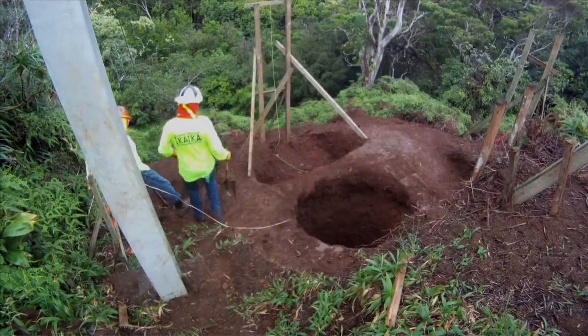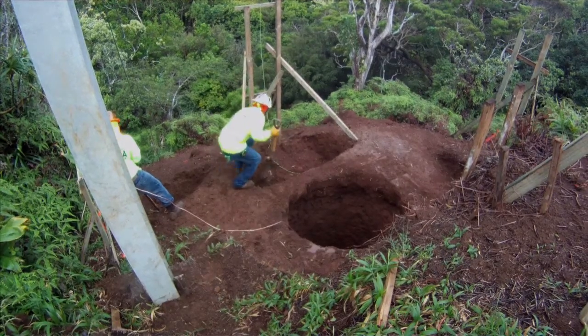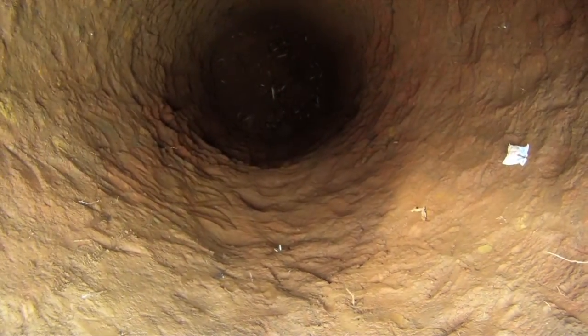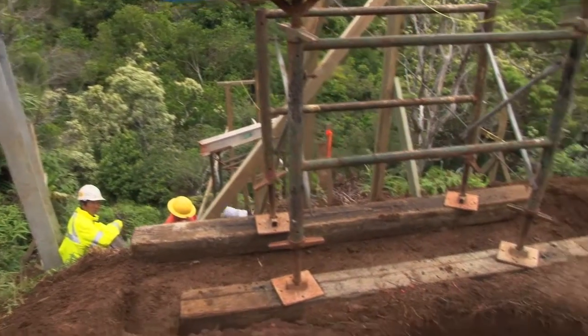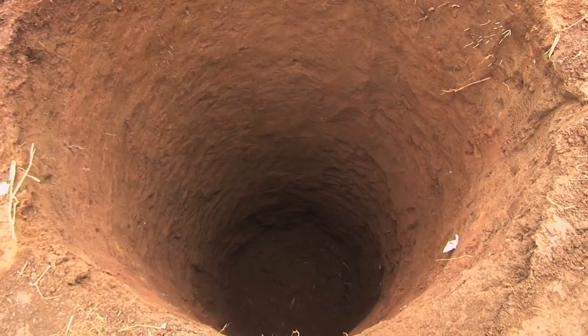First, contractors have flown in to dig the holes for the foundation. A typical foundation might be five feet in diameter by 15 to 20 feet deep, but can be bigger depending on structure size, soil type, and topography. A compressor and air tools may be airlifted in, but all that soil from the hole has to be pulled out by hand and five-gallon pails.